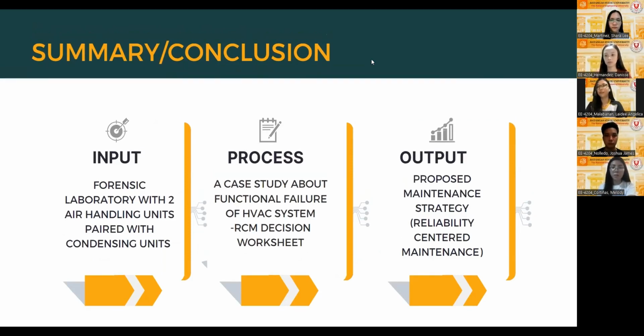Conclusively, this case study number 2 revolved around the reliability-centered maintenance of a commercial heating, ventilation, and air conditioning system. It has presented a case of a forensic laboratory with 2 air handling units paired with condensing units connected to the building management system, which continuously monitors both the running system and one on standby. So with the use of the RCM information sheet, the needed information for each component of the HVAC system was presented along with the function failure of the component and its failure mode. Also, the information sheet includes the possible effects caused by the function failure.